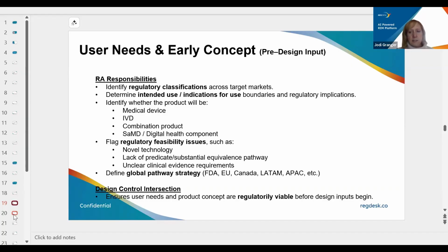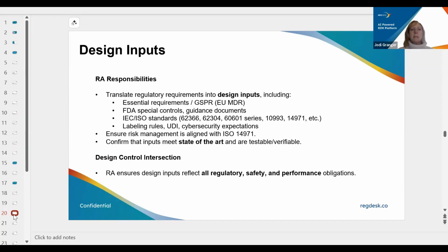So that's the first phase of the design process. The second is in regards to design inputs. This is where you start to get much more detail in terms of being able to assess the regulatory requirements in each of the target markets, determine what essential requirements need to be met. Are there special controls for this specific device? Are there guidance documents specific for this type of device? Are there standards, and what are those standards that you need to comply with?